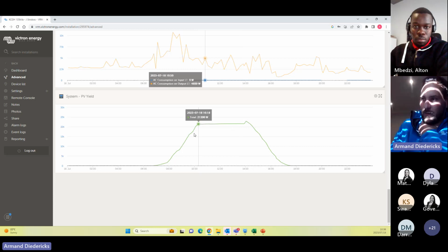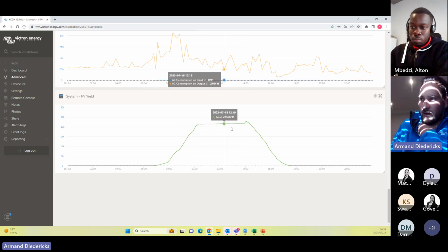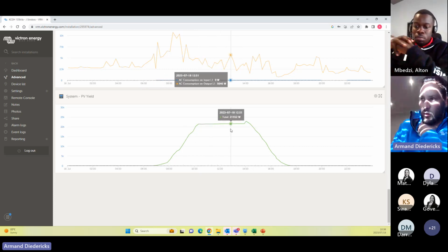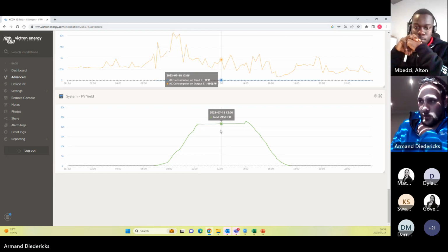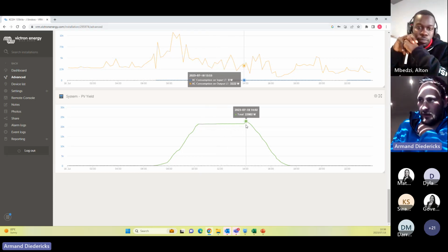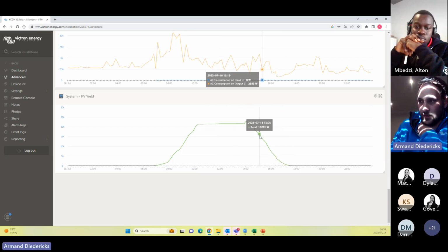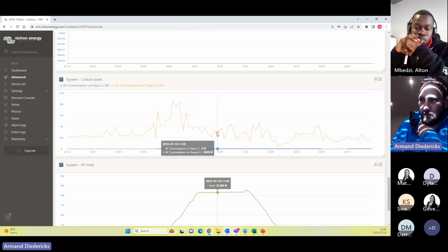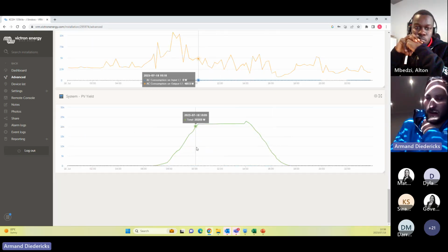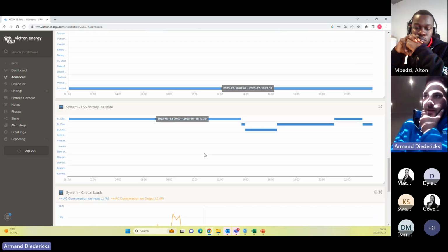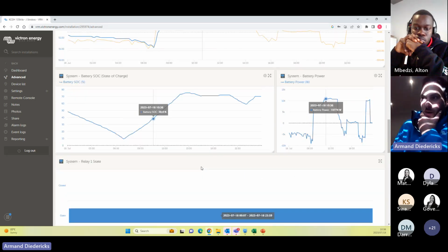You can see they didn't get the bell curve - obviously they got limited, there's no more load and the batteries are full. So it limits, then peaks, then drops down. You can actually go look at each MPPT and see if all of them are working the way they should.